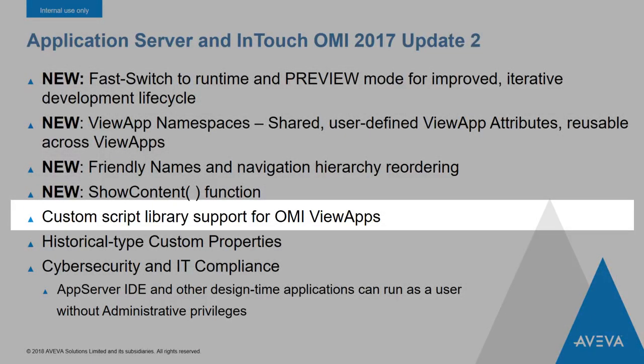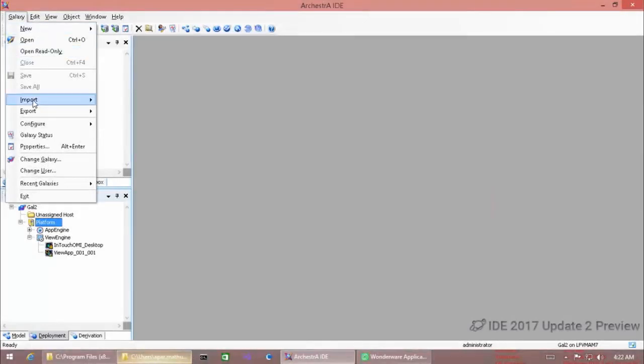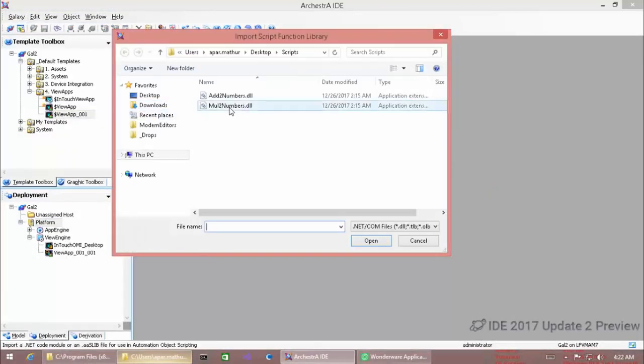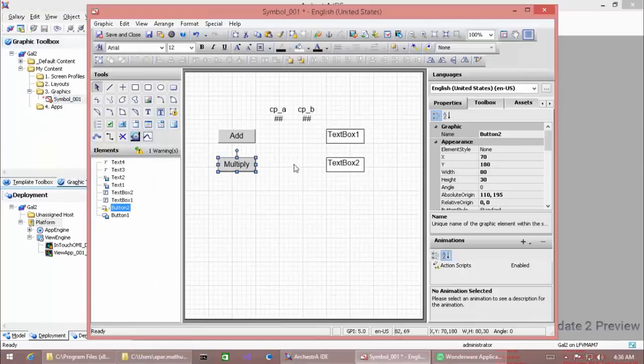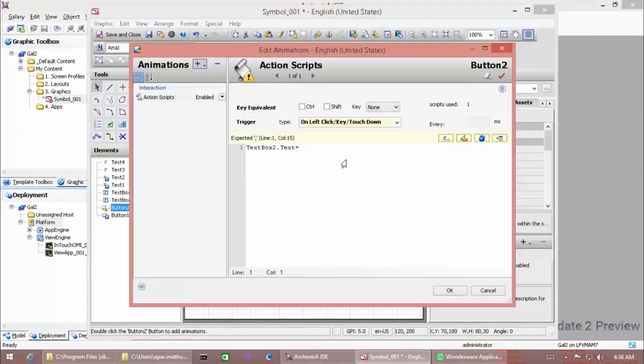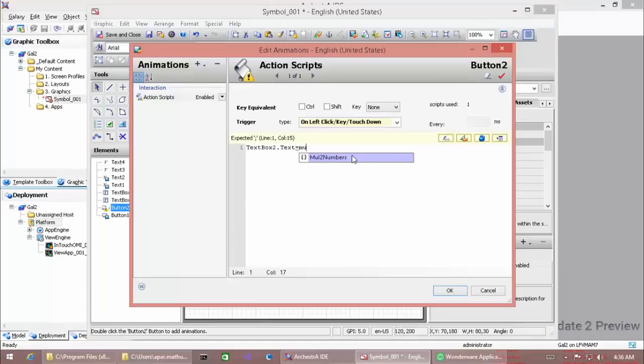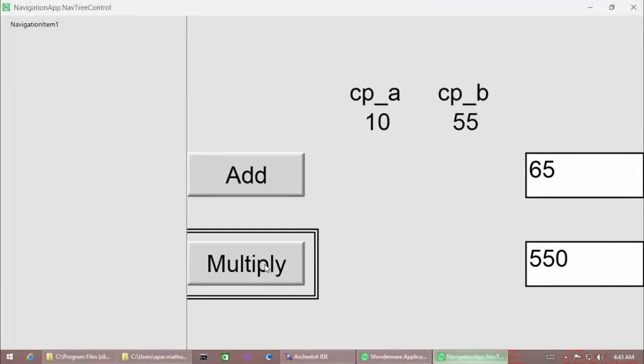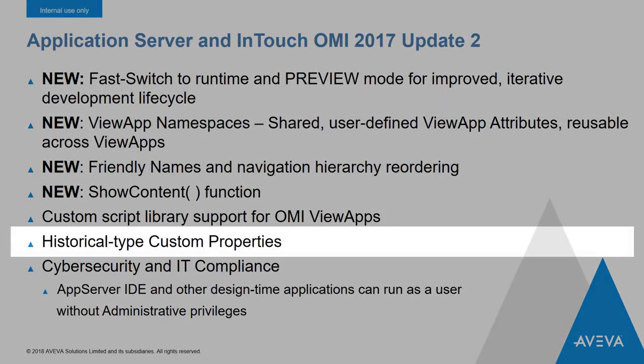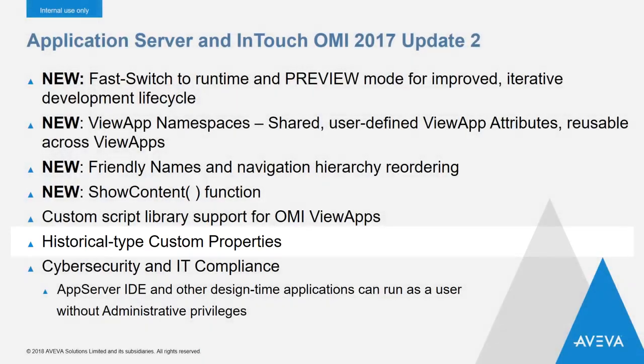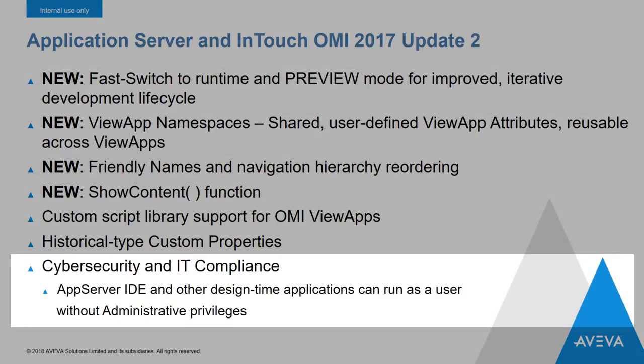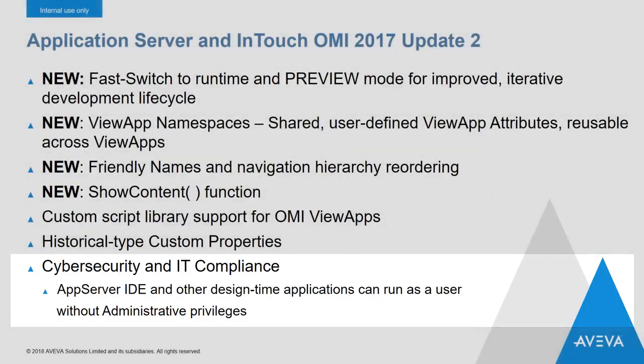We've also added support for custom script libraries in the InTouch OMI runtime. This allows you to import your existing custom script libraries and then use them within ArchestrA Graphics when they're displayed in the InTouch OMI runtime. Expanding on that type of support, we've also added the ability to use the historian type custom properties within ArchestrA Graphics and ArchestrA Graphics scripting in InTouch OMI. And in the area of cybersecurity and IT compliance, you can now run the IDE and other design time applications as a user that doesn't have administrative privileges. This greatly reduces the size of the attack surface for connected systems and is becoming a mandatory requirement for many industries.